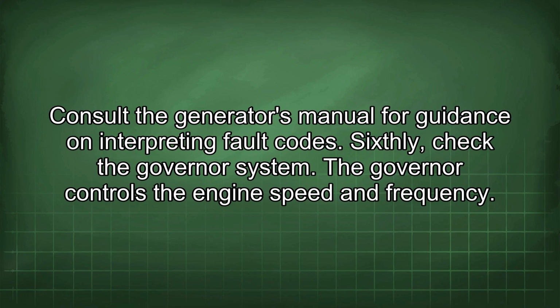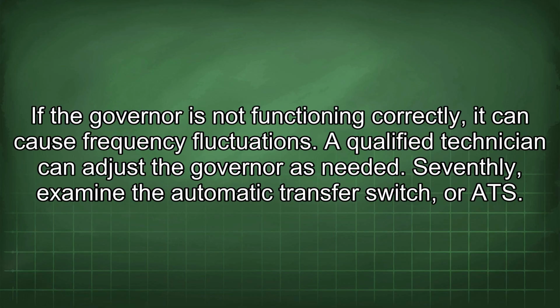Sixthly, check the governor system. The governor controls the engine speed and frequency. If the governor is not functioning correctly, it can cause frequency fluctuations. A qualified technician can adjust the governor as needed.